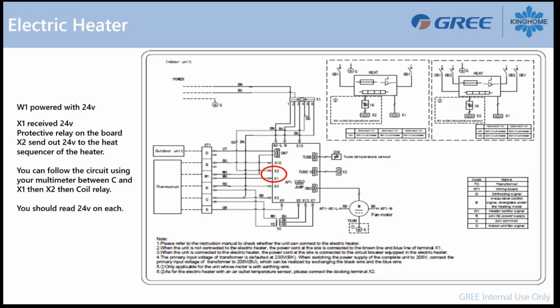On the board, you will see two different connections. One is called X1. From your aux connection, you will have 24 volts sending to X1. And then the internal section here will wait to have the blower motor running before sending the 24 volts on X2, on your plug, to activate the duct heater. So this is really important.